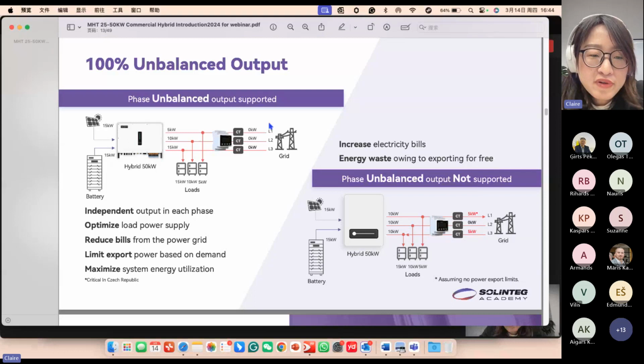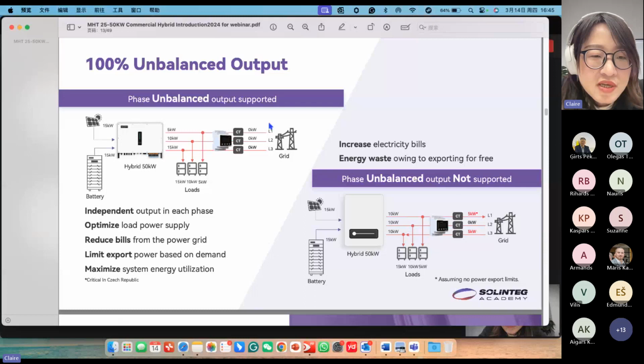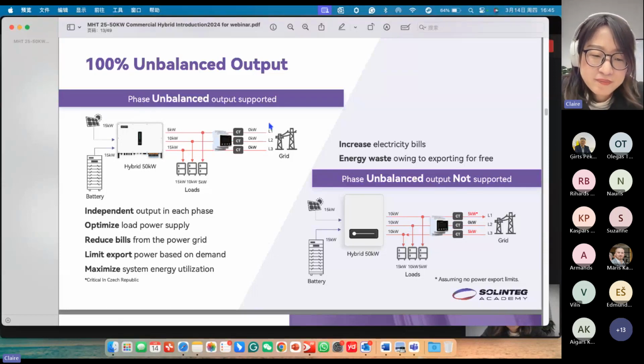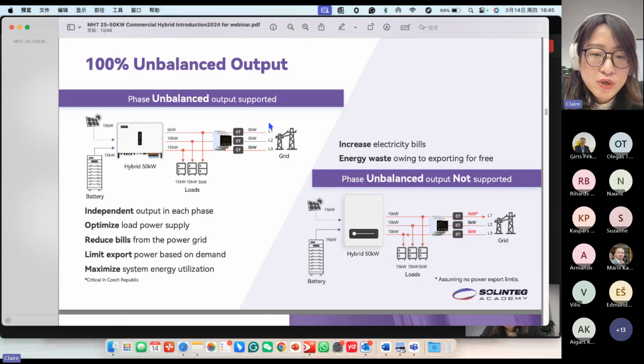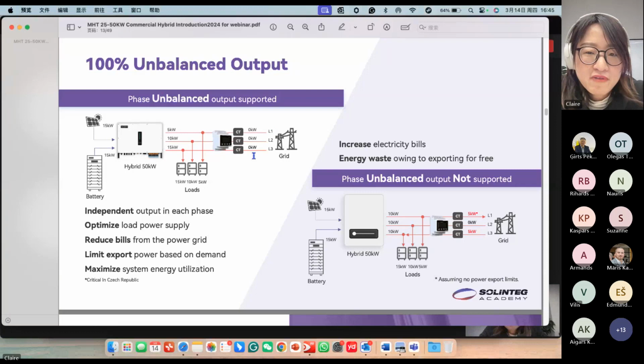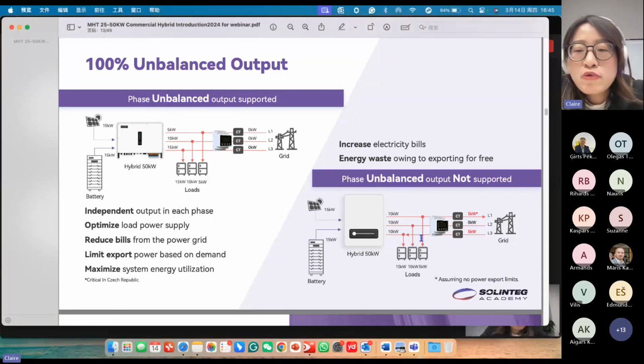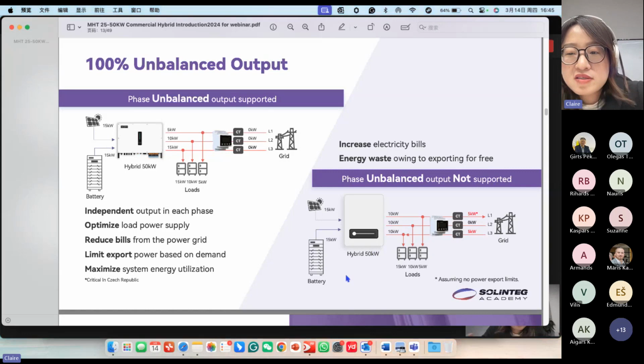So we also, for this series inverter 2550, we support 100% unbalanced output. And for the other series, like 4 to 20 series, we support up to 110% unbalanced output, which my colleague Yaroslav just explained before. So here we can see a case. On the right side is an inverter without the unbalanced output. We can see different loads connected in different phases. The first phase is 5 kilowatts, and the second one 10, third one 15.